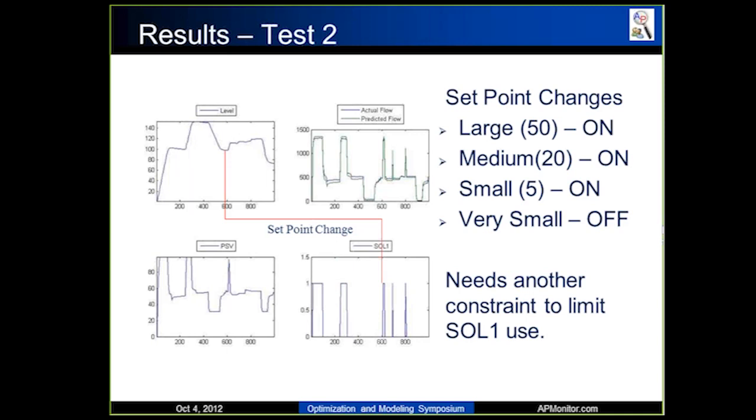But basically what I noticed is that for large setpoint changes, it'll turn the solenoid valve on. For medium ones, it'll turn it on. For small ones, it'll turn it on. But for very small setpoint changes, these are like one or two millimeters, it won't turn on the solenoid valve. It'll simply just use the PSV to change the flow rate. So it's smart enough to figure out it doesn't need to turn on the discrete valve to make it work.